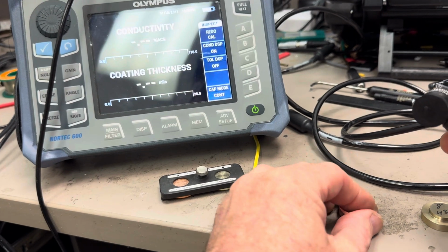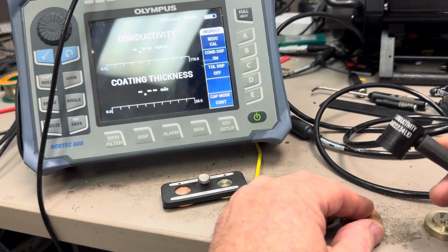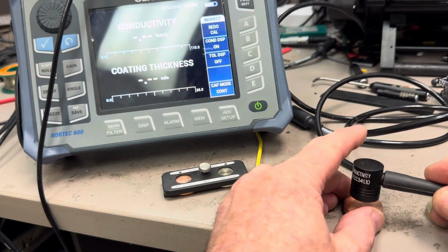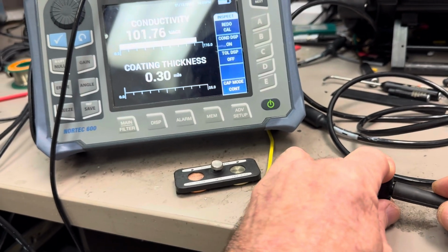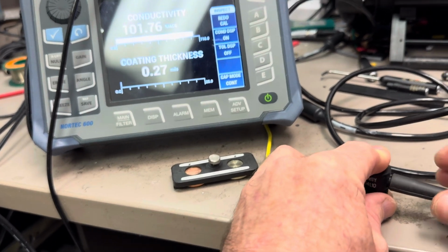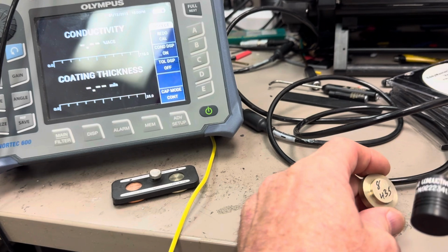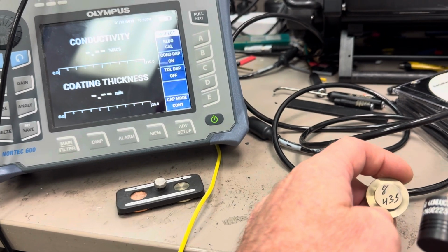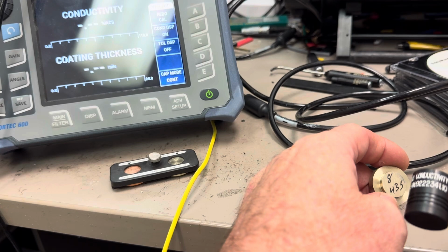I mean, it's an expensive tester. It's a late model, used by aircraft and all other sorts of companies with a specific probe, and it gets pretty close. It's not right on. It's an estimate. All Eddy current results are estimates because they're comparing one thing to another.